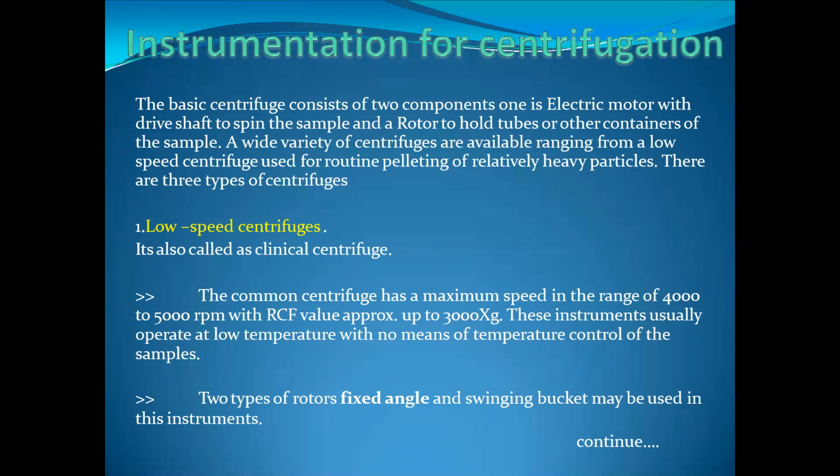Low speed centrifuge, also known as the clinical centrifuge. The common centrifuge has a maximum speed in the range of 4000 to 5000 rpm, with an RCF value of approximately up to 3000 × g. These instruments usually operate at room temperature with no means of temperature control of the samples.